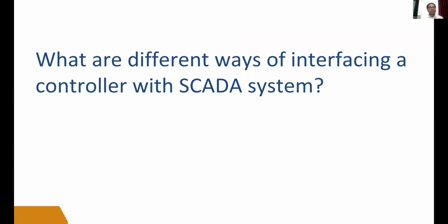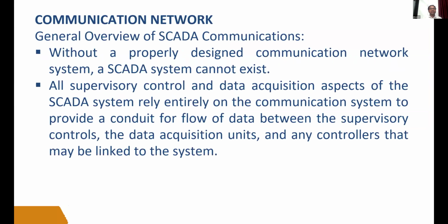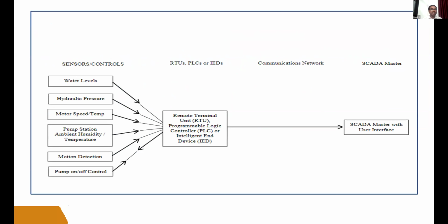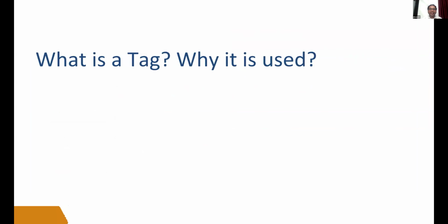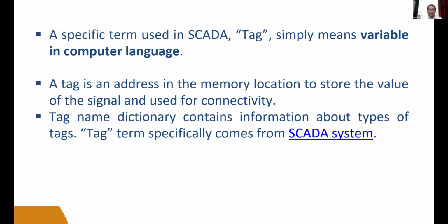And what are the different ways to interface the SCADA with your controller? So definitely, as I have shown here in this diagram, there are different sensors and controllers. They can easily be configured to the PLC or RTU, and based on your PLC program, you can give the tags to the SCADA. And what is meant by tag? So in a PLC program or any other program, you must have seen the instructions. So in SCADA, instruction is replaced by a tag. As an instruction, you can use the tag here.